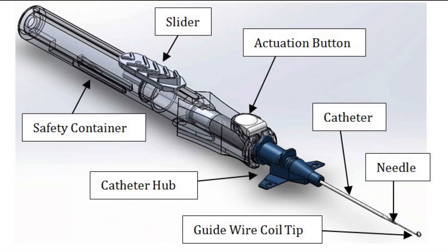Today we're going to talk about the AccuCath device, produced by Vascular Pathways. It's a peripheral IV with an integrated guide wire to allow easier insertion. Here you see a diagram showing a longer handle, which is your needle safety device, with the actuation button to retract the needle with a spring. You see the slider to extend the wire, the catheter, and the catheter hub.